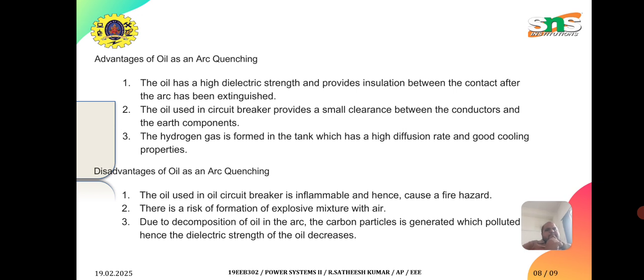Advantages of the oil circuit breaker. The oil has a dielectric strength and provides insulation between the contacts after the arc has been extinguished. The oil provides a small clearance between the conductors and the earthed components. The hydrogen gas formed in the tank has a high diffusion rate and good cooling properties. Drawbacks. The oil used in oil circuit breakers is inflammable, hence it causes a fire hazard. There is a risk of formation of an explosive mixture with air. Due to the decomposition of the oil, carbon particles are generated, which pollute the oil.